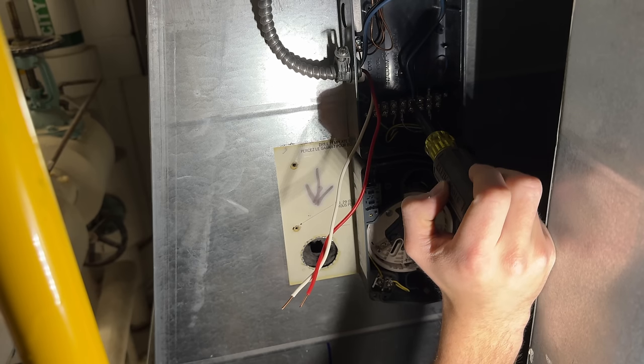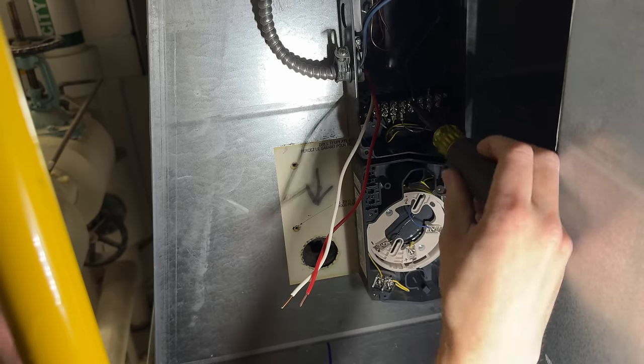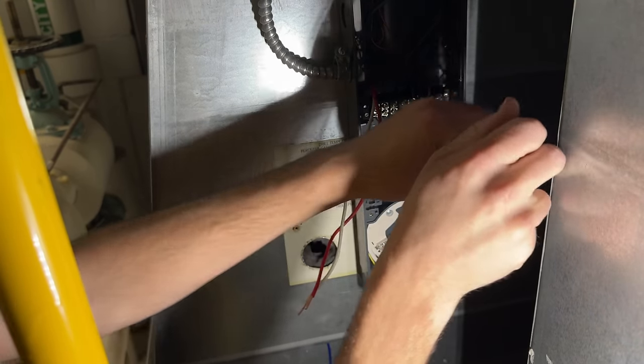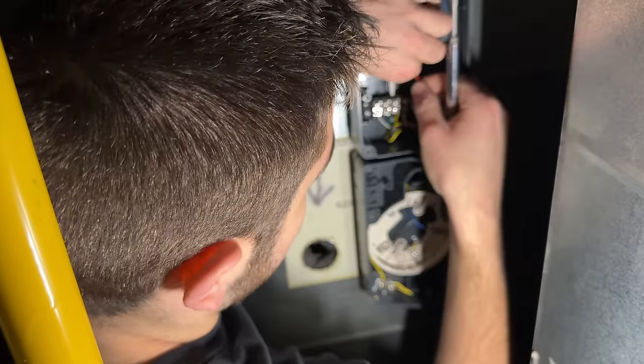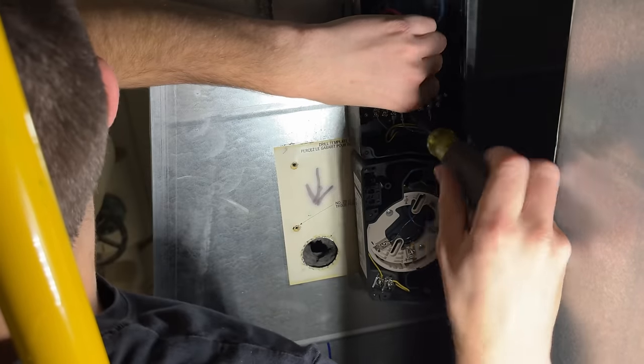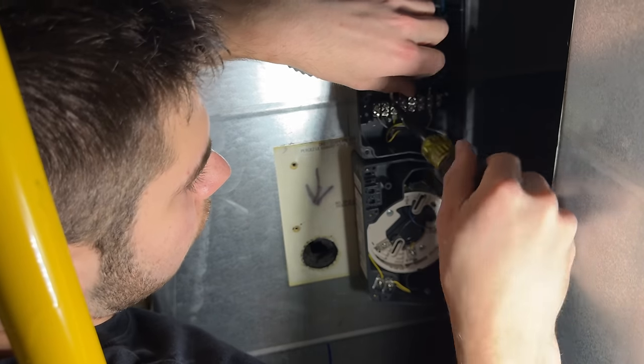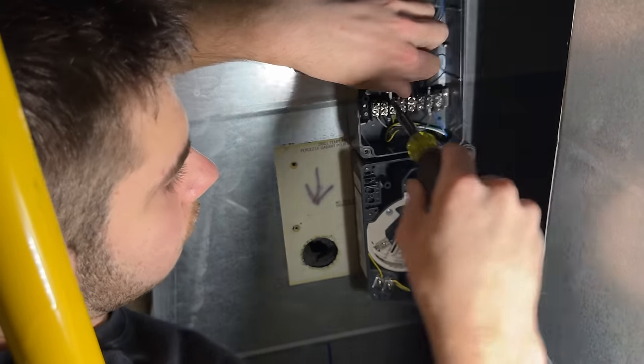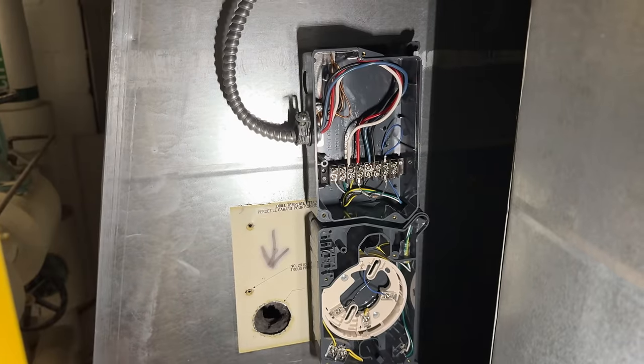The duct detector, that'll make things easier depending on how you're trying to mount it. Well, like that one there, and yours up high, the airflow is different than your lower ones. Yep. Nice. Is there a red cap to go over the end? Yes. Oh, yeah, I see it. Or is that supposed to go where it looks for? The red cap goes on the end of the sampling tube. Okay, so the airflow is coming this way.